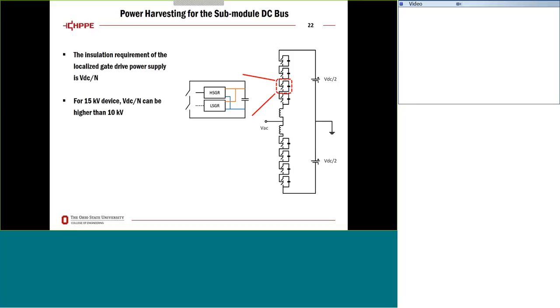So again, we're taking the power from the submodule DC bus, and each submodule DC bus only has a small portion of the overall DC voltage. But for a 15 kV device, this DC voltage can be more than 10 kV, and if we are using a 20 kV device, it would possibly be 15 kV or even higher. So we are talking about implementing an isolated DC-DC converter with a 10 kV input and 15 watt output.